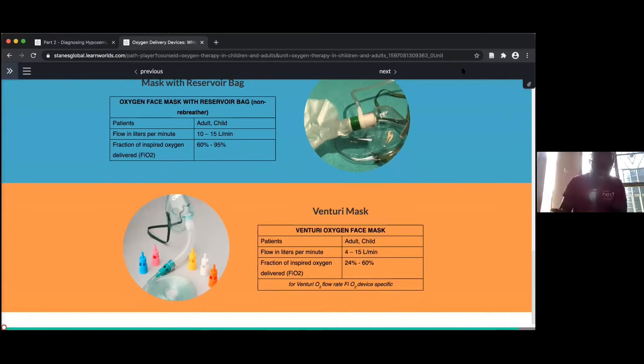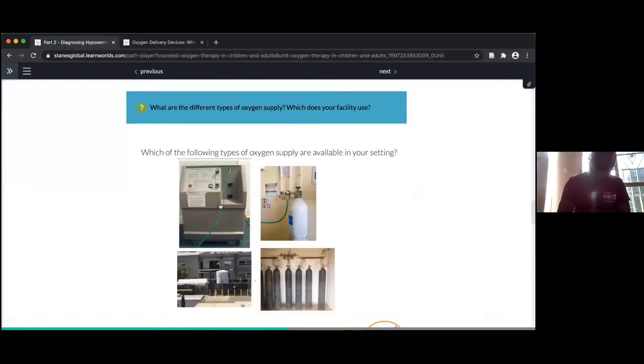You go to the cylinders. For the concentrator, many of the maintenance tasks are easy and everyone can do them. Behind the concentrator, there is a filter. You can just wash it with water, clean it, and put it in the sun. When it's dry, put it back again. Because if you don't clean it, it ends up obstructing the sucking in of the air to be concentrated into oxygen.